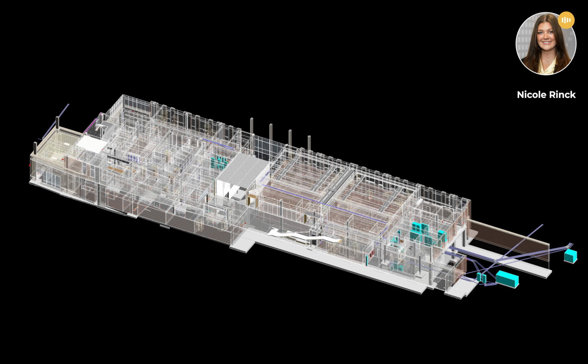Detection devices like smoke detectors and pull stations send an alert to the fire alarm control panel that there is a fire. The fire alarm control panel then commands the notification devices to operate. The notification devices like speakers and strobes send visual or audible signals across the building so that they know they need to exit. All of these elements are the basics for laying out an electrical system in your high school.